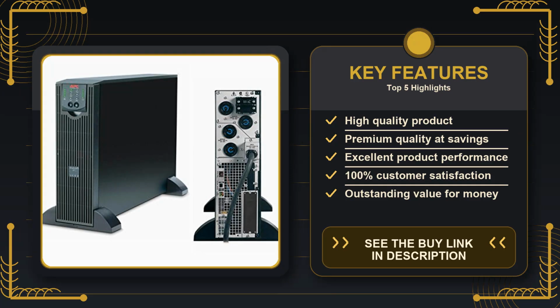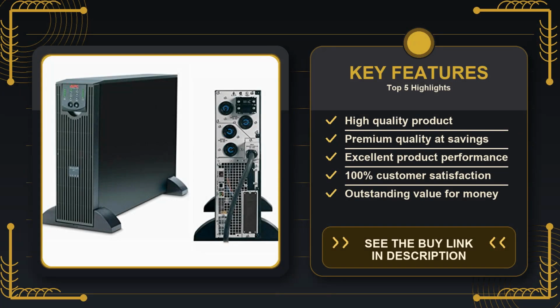Another practical point is the smart part of the name. This isn't just a battery that turns on—the unit talks to your network via Ethernet, letting you monitor voltage, battery health, and load levels from a web portal or through APC's PowerChute software. I've seen this in action on a friend's co-working space. When a surge hit the building, the UPS logged the event, sent an email alert, and the admin could see exactly which devices were drawing power at the moment. That visibility can save you from the classic 'I thought everything was fine' until the next morning's crash report. It also means you can schedule battery tests during off hours without having to physically open the case.